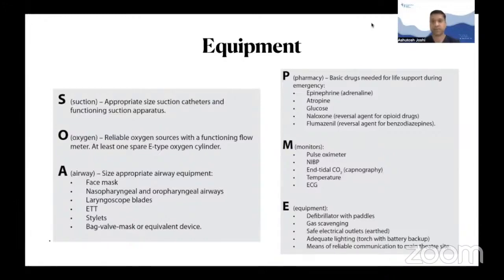Standard monitoring should always be available. And E stands for special equipments such as defibrillators with paddles, gas scavenging system, extra safe electrical outlets, adequate lighting, as well as means of reliable communication to the main theater site.